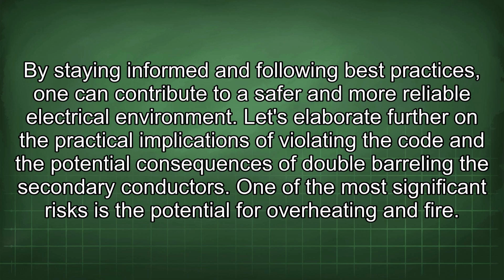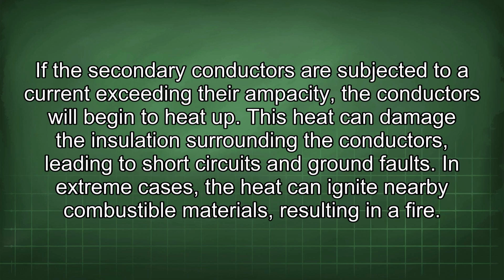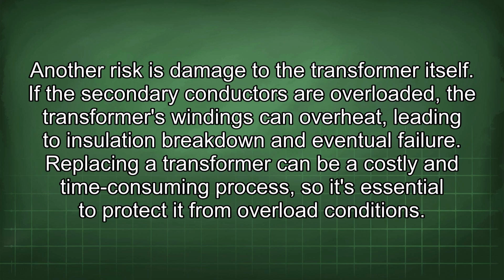Let's elaborate further on the practical implications of violating the code and the potential consequences of double barreling the secondary conductors. One of the most significant risks is the potential for overheating and fire. If the secondary conductors are subjected to a current exceeding their capacity, the conductors will begin to heat up. This heat can damage the insulation surrounding the conductors, leading to short circuits and ground faults. In extreme cases, the heat can ignite nearby combustible materials, resulting in a fire. Another risk is damage to the transformer itself. If the secondary conductors are overloaded, the transformer's windings can overheat, leading to insulation breakdown and eventual failure. Replacing a transformer can be a costly and time-consuming process, so it's essential to protect it from overload conditions.